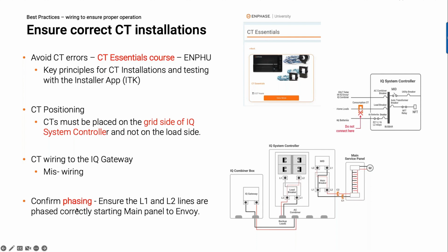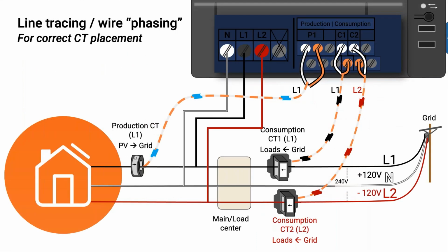And then phasing is the last one. So I'm going to spend just a little bit of time talking about phasing because this is just one of those things where installers miss this. Phasing is the perspective of when measuring power for the system to get the system to behave properly. Measuring power for the system, we're measuring power for two phases. Like all of you know, we have split phase systems, so we have power that's drawn from line 1 and from line 2, and then we add them together to get the total power for the system. Now, in order to measure power for line 1 and power for line 2, we have to measure voltage and current for each phase.